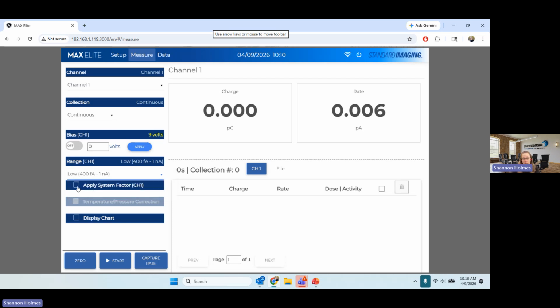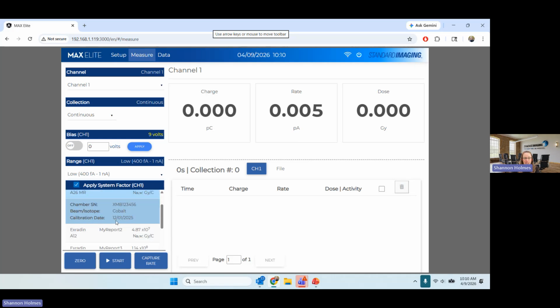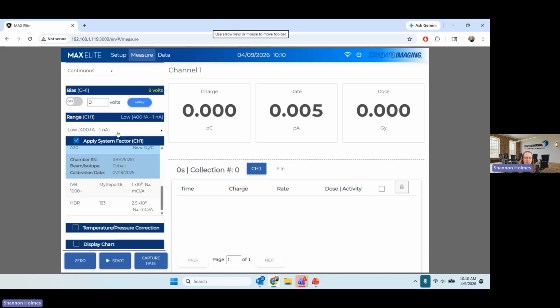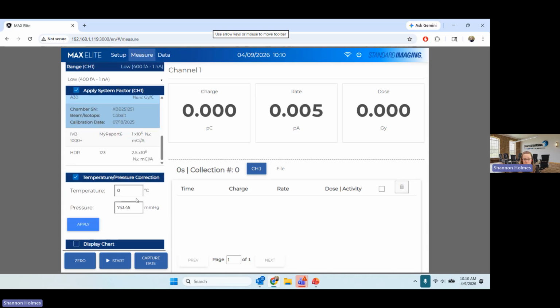If you want to apply a dose calibration, you can apply a system factor and select which chamber you want to use, which calibration you want to use. And then you can also select whether you want to apply a temperature pressure correction factor. We autofill the pressure based on a sensor that's in the unit itself. But since temperature has to be at the location of your probe and not the location of the electrometer, we can't autofill that for you. So if we put in a temperature here and apply that, it will give me a little thermometer icon on my dose value to let me know that I have applied that temperature and pressure correction factor.